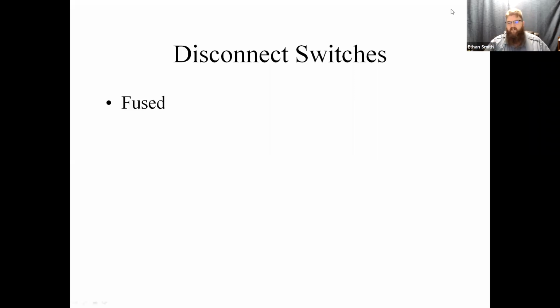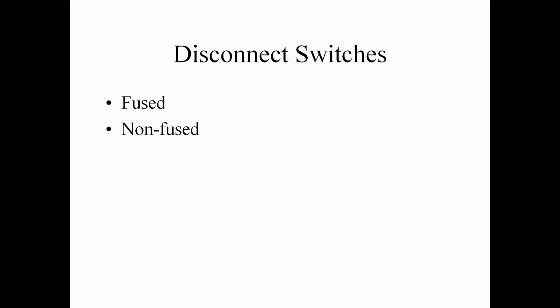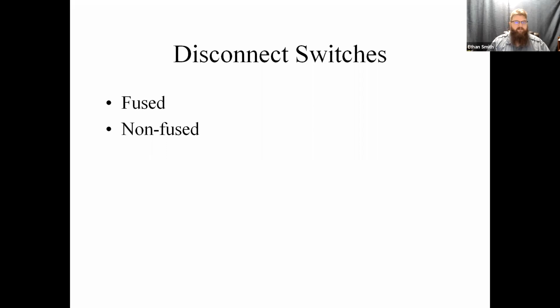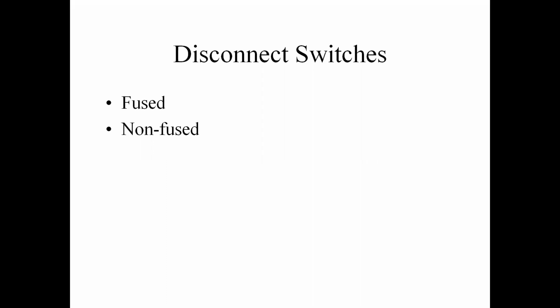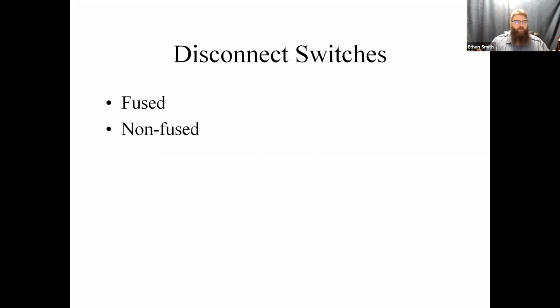Now, the thing that people get hung up on is, I already have a breaker. Why would I need a fused disconnect? Why can't I just use that non-fused disconnect? What do you guys think? What's the job of a fuse in a disconnect switch? Why would we put a fuse in a disconnect switch? To prevent a fire. Okay. Any others? In case your breaker didn't work. Okay. So fuses are there to protect the equipment. Is that a fair statement?